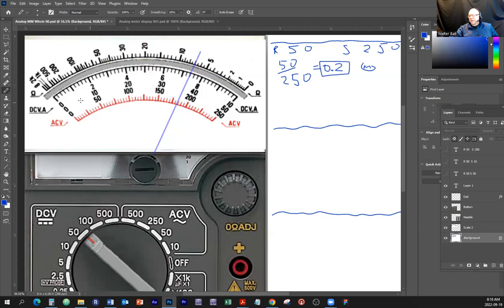So we got 0, we got 50, so somewhere in the middle that is 25: 5, 10, 15, 20. So it looks like every single division gives you 5 volts. All right, so we're on the scale of 250. So 150 here, we have 150, and 200 here. And if every little division equals 5 volts, then 155, 160, 165, 170, 175, 180, 185. So we're reading 185 on the scale of 250.